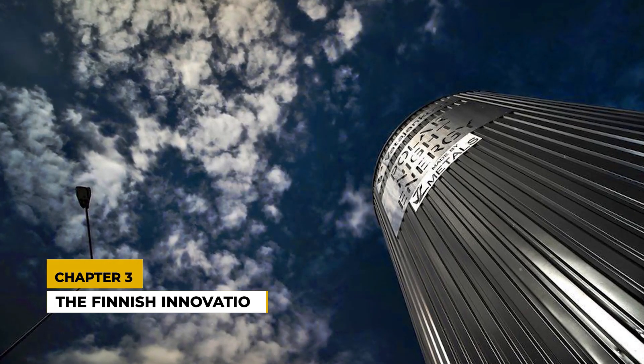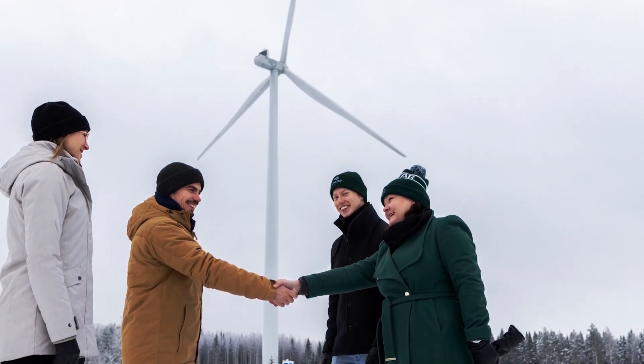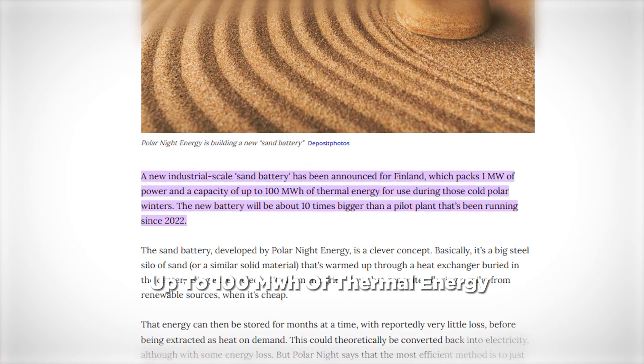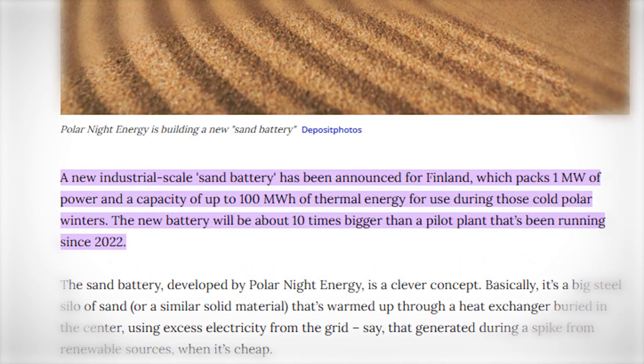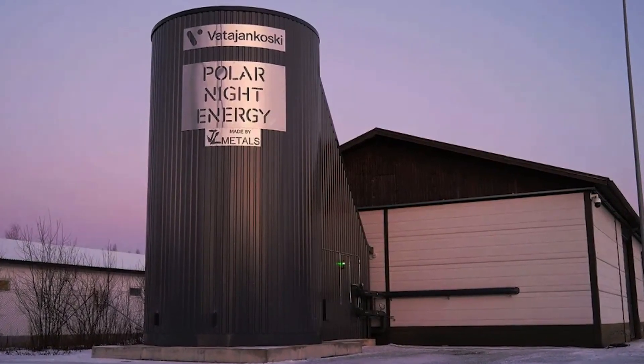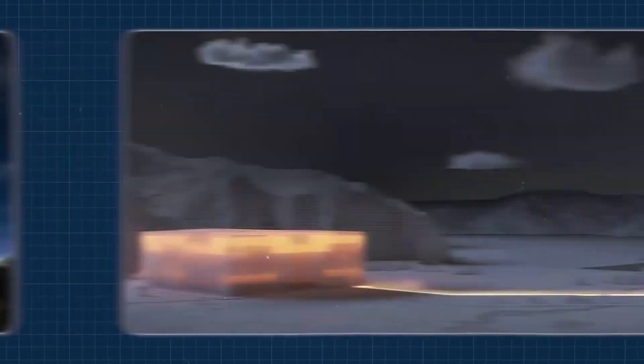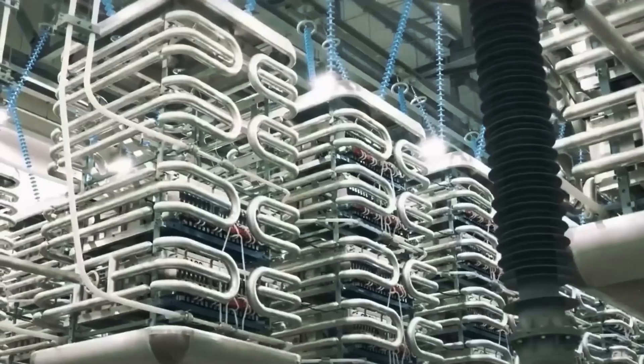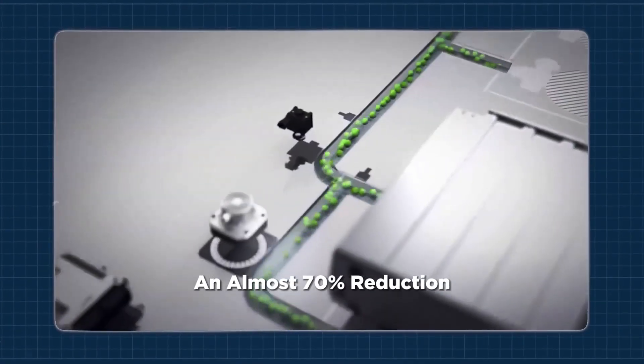Chapter 3: The Finnish Innovation. Polar Night Energy, a Finnish company, has taken sand battery technology to new heights. Their latest project is a massive sand battery capable of storing up to 100 MWh of thermal energy and delivering 1 MW of power. The new sand battery stands an impressive 13 meters tall and 15 meters wide. This battery can meet the heating needs of the Finnish municipality of Pornainen for a week in winter or a month in summer. Additionally, the battery is expected to significantly reduce the district heating system's carbon dioxide emissions by 160 tons per year, achieving an almost 70% reduction.